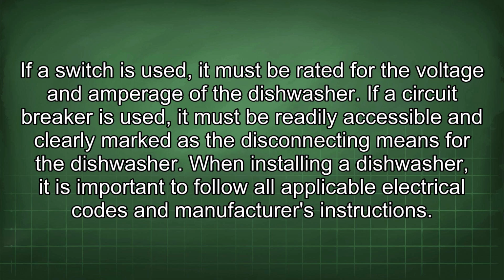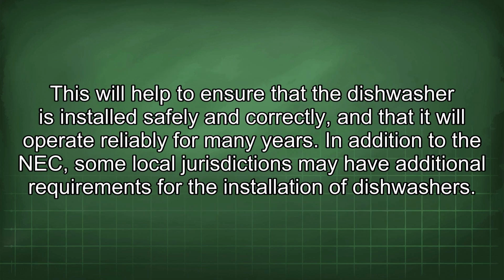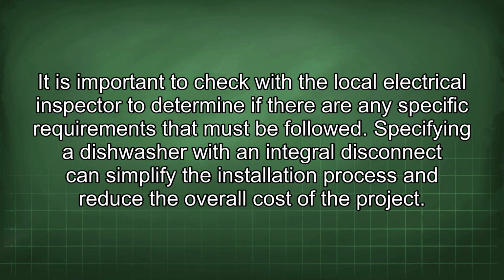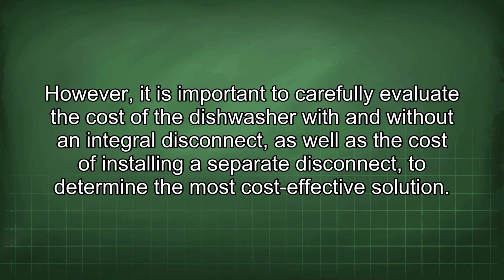When installing a dishwasher, it is important to follow all applicable electrical codes and manufacturer's instructions. This will help to ensure that the dishwasher is installed safely and correctly, and that it will operate reliably for many years. In addition to the NEC, some local jurisdictions may have additional requirements for the installation of dishwashers. It is important to check with the local electrical inspector to determine if there are any specific requirements that must be followed. Specifying a dishwasher with an integral disconnect can simplify the installation process and reduce the overall cost of the project. However, it is important to carefully evaluate the cost of the dishwasher with and without an integral disconnect, as well as the cost of installing a separate disconnect to determine the most cost-effective solution.